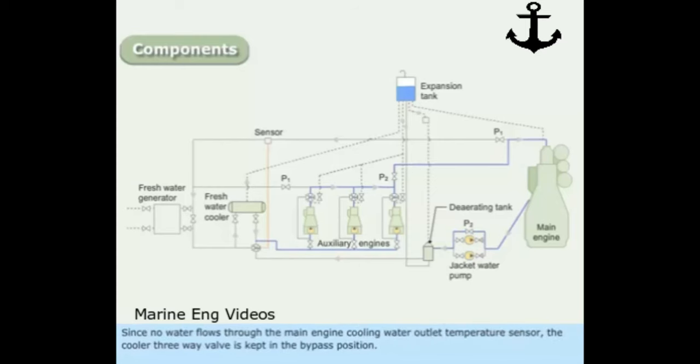Since no water flows through the main engine cooling water outlet temperature sensor, the cooler three-way valve is kept in the bypass position.